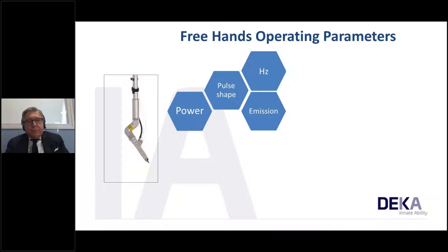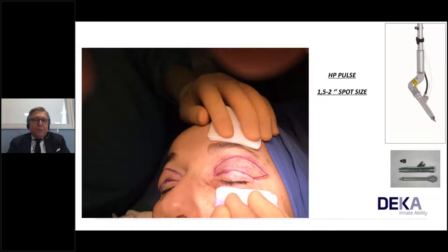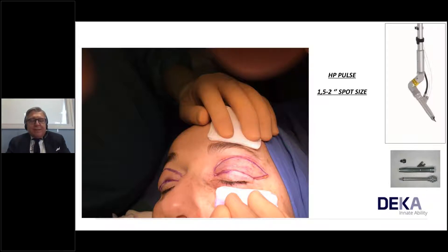Freehand operating parameters for the 1.5-inch piece: pay attention to power, pulse shape, frequency, and emission. Using HP pulse in freehand mode with the 1.5-inch spot size, we can appreciate the sharp demarcation of the cutting incision area. This allows operation in a clean surgical theater with minimal or no bleeding.